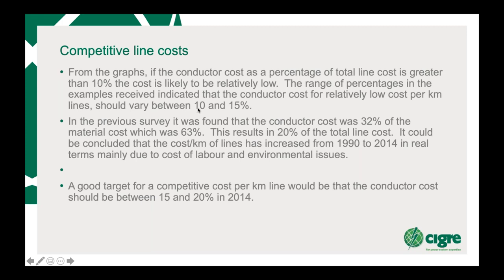So if you can say get a line which has got so many millions per kilometer, and they say, well, is that line a good value for money? And you can work out the ratio of the conductor to the total cost, and it's say 20%, you can say, well, yes, it's actually a very good line design. If it comes in at 5%, you say, well, maybe we should relook at some things because something's not right here. The construction cost is too high, or the foundation costs are too high.